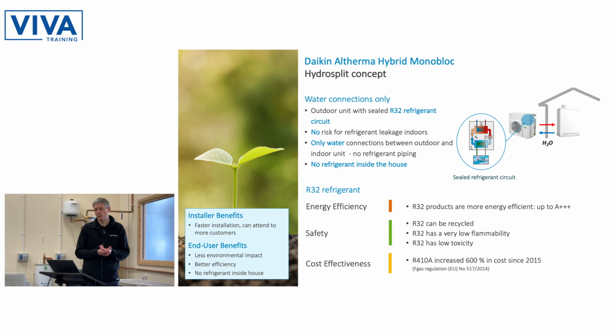So I mentioned before, this is our hydro split concept. Unlike the first generation of hybrid, it's only water between the indoor unit and the outdoor unit. So the refrigeration system is completely contained within the outdoor unit. No refrigerant can possibly leak indoors. Some people are concerned about things like that, although they're quite comfortable having fridges and freezers in their kitchen. So no, it's not a concern, but some people think that's something they don't want.